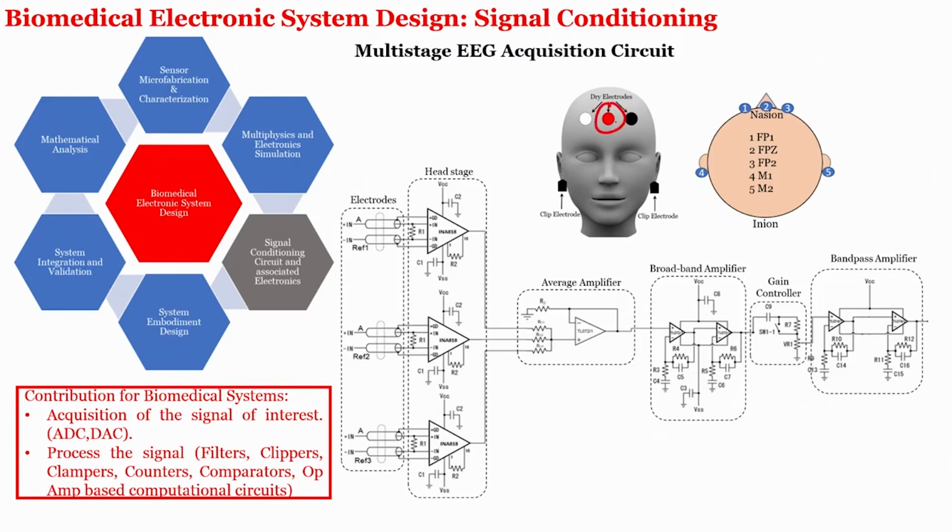Then there is the occipital region just at the back, right, which is used for visualization. Then there is a temporal region, there is a central region. So, there are several regions in the head that are divided into different parts, so as to understand where to keep the electrode. Now, generally you may have seen that the 10-20 system is used for measuring this EEG signal. However, for a certain application, right, and of course, you have to have a reference and ground that you already know.